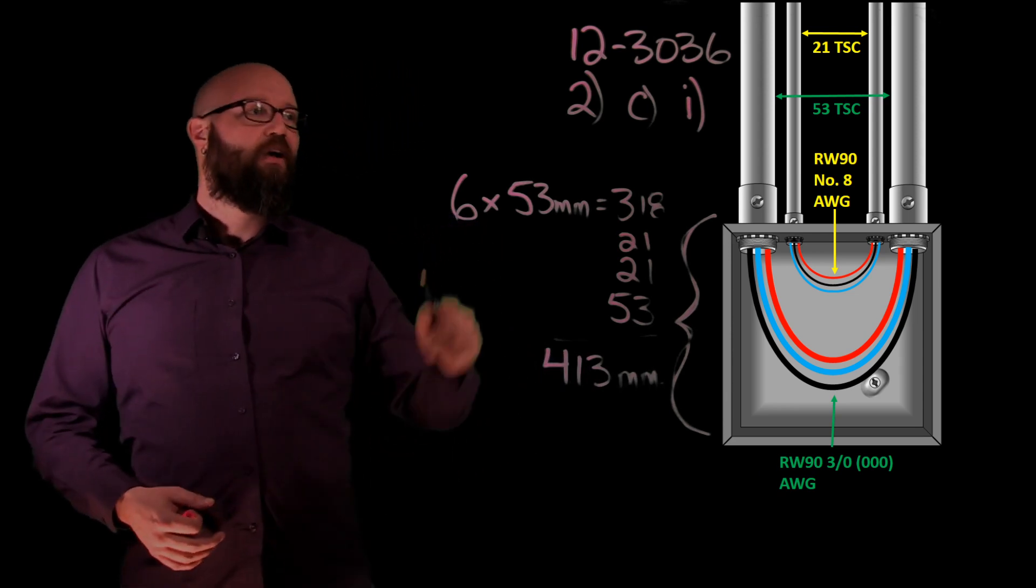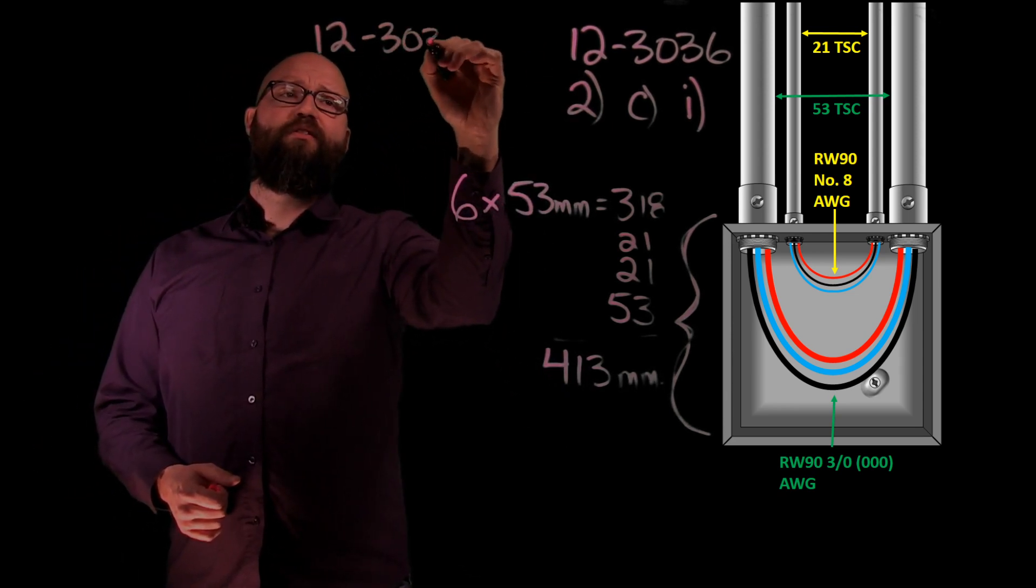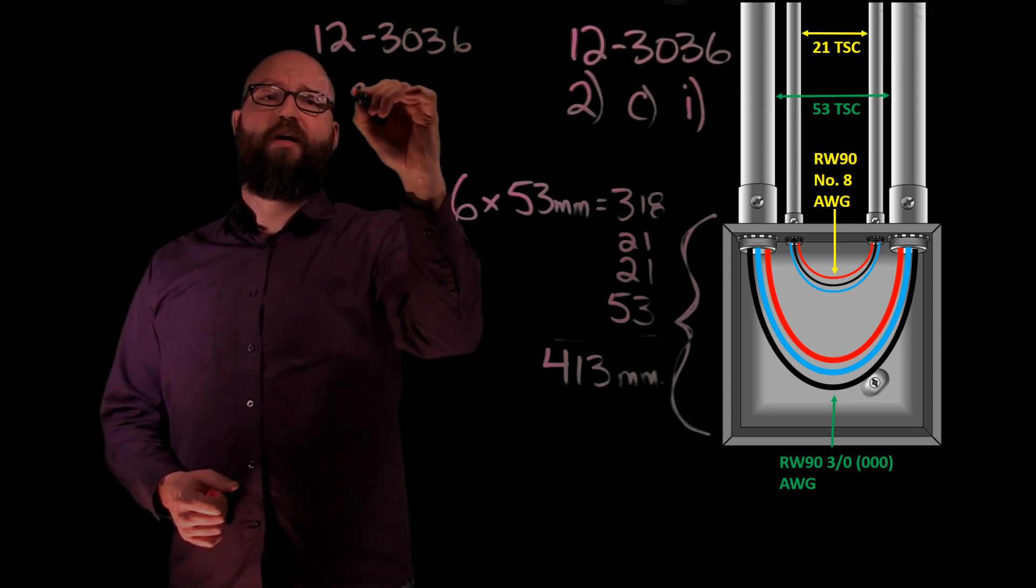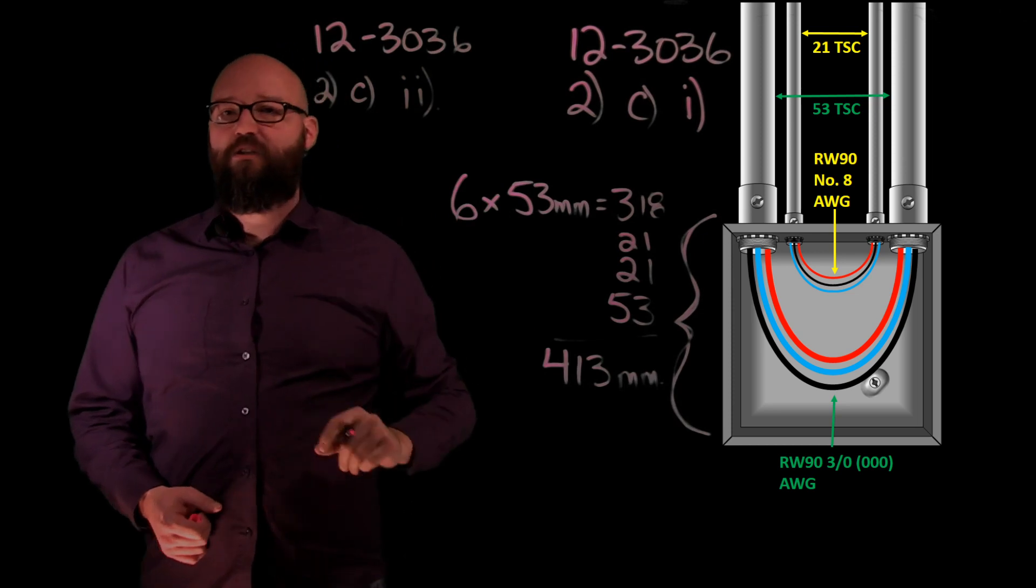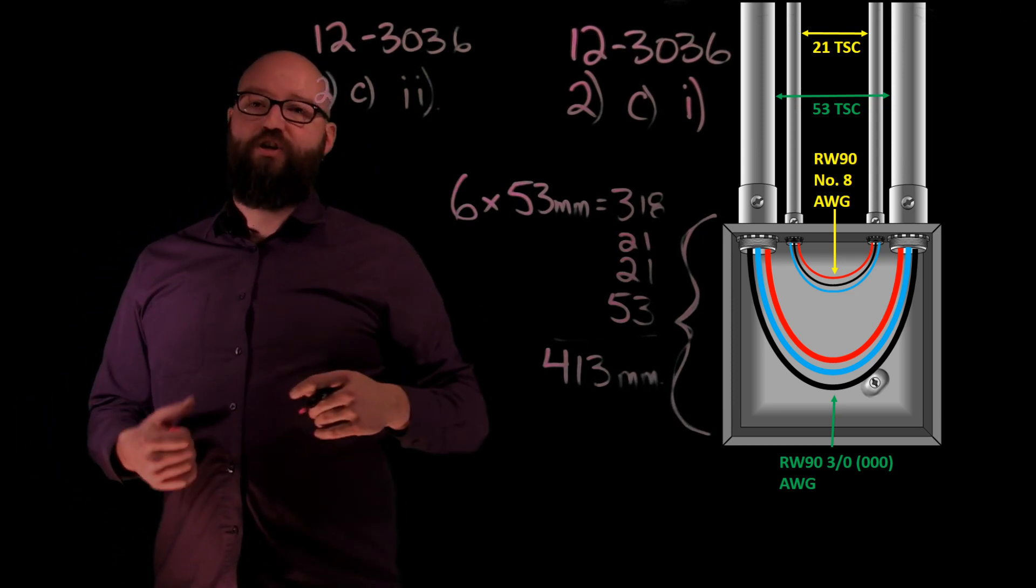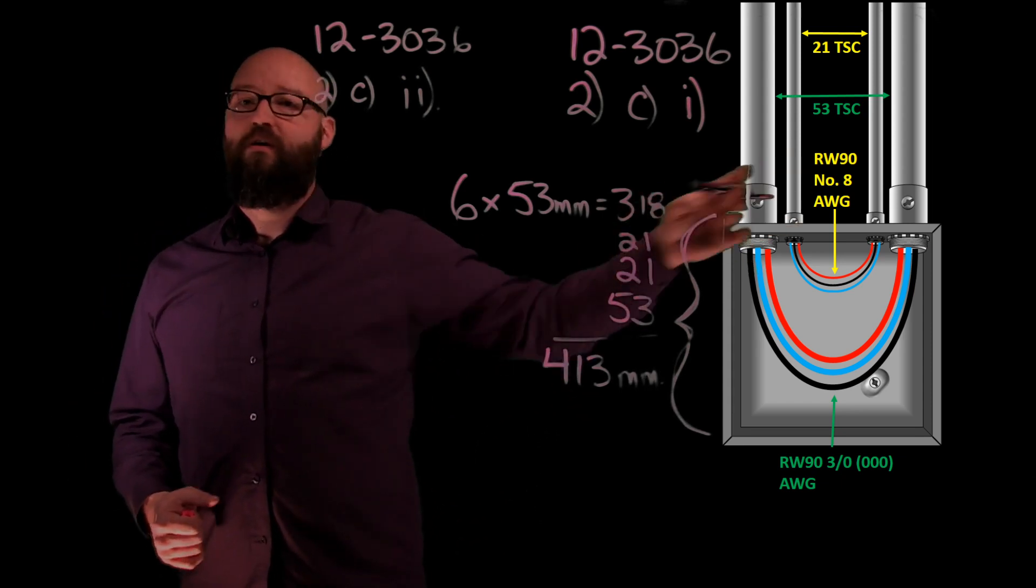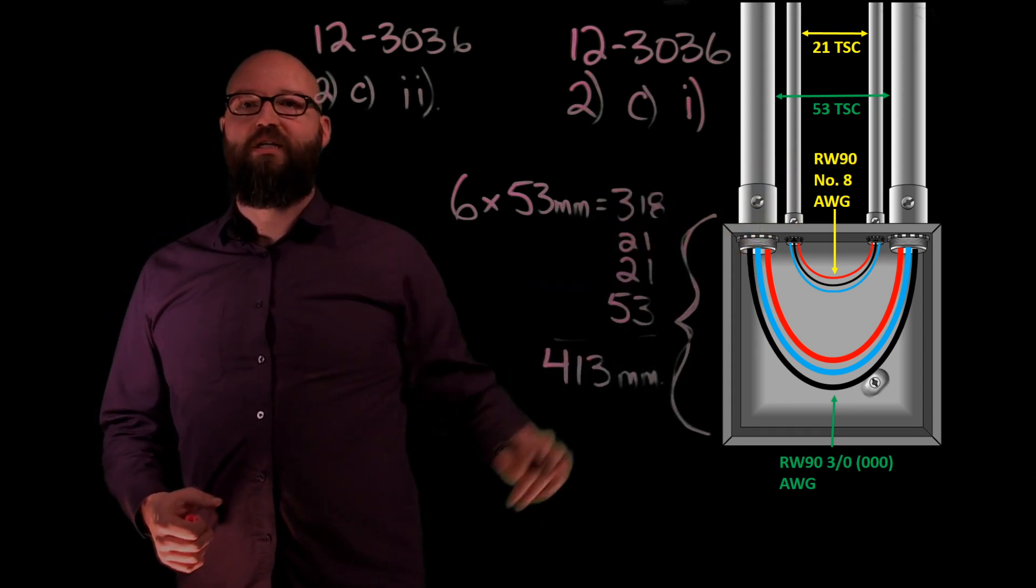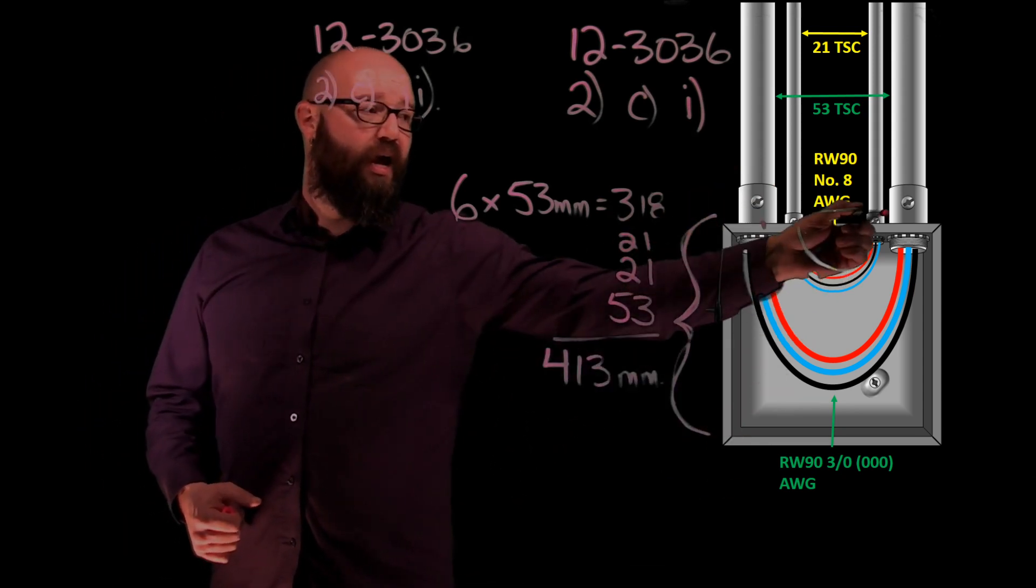So what it tells me if I look at 12-30-36, if I go 12-30-36 sub rule 2 item C but now we're looking in I-I, it tells me that to observe that proper bend radius or to make sure that I have six times the largest trade size conduit of the conduits that contain those conductors. Right, so our three oughts start here and end here.